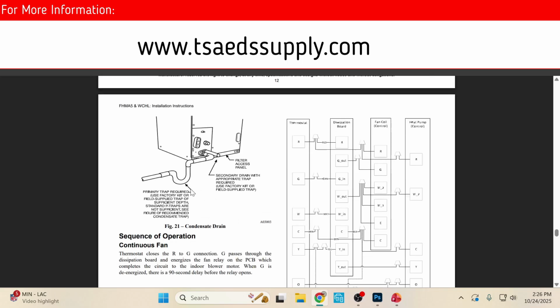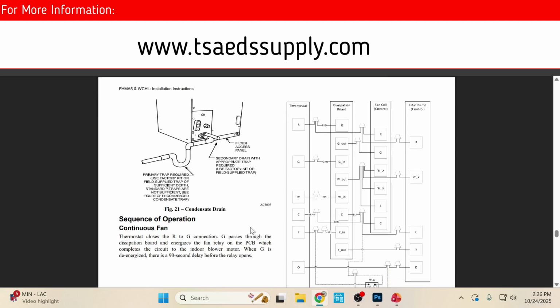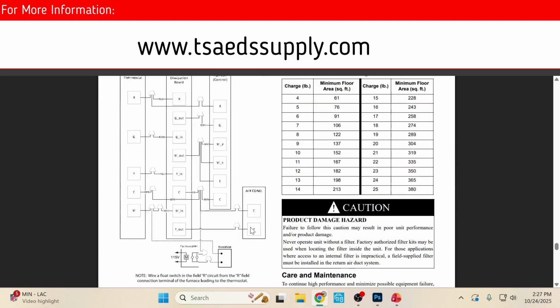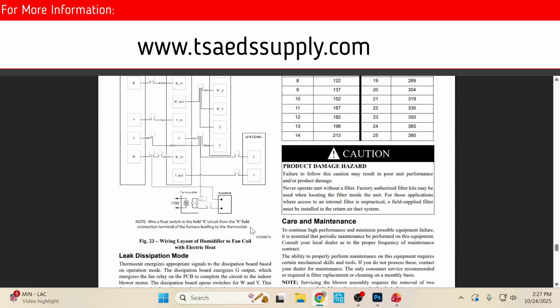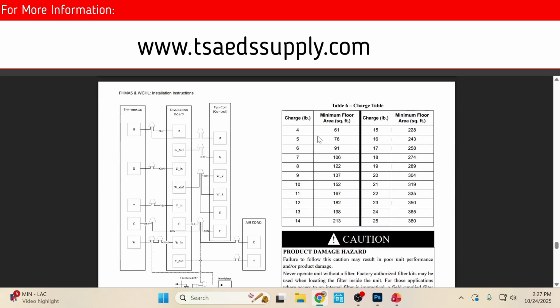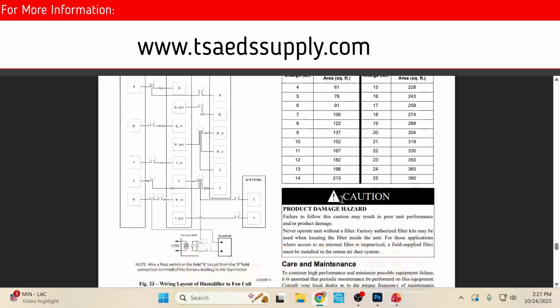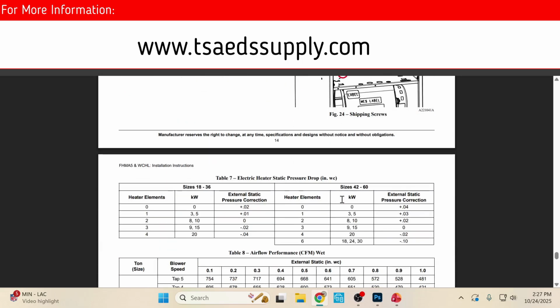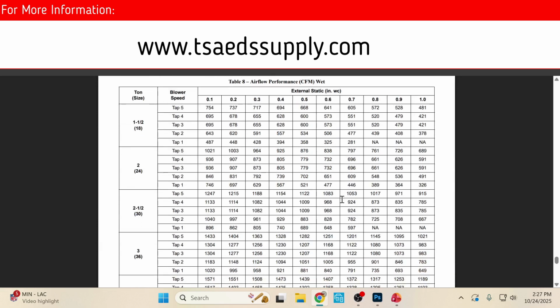Again, here is the big U-trap. Make sure you're looking at this manual when you actually set your traps up. This is something you're going to see in the manual: if I have 8 pounds of charge in my system, I have to make sure I have 122 square feet minimum, so that if there is a dissipation system or there is a leak, I've got enough room that it will not be flammable when it discharges. So here's where I wanted to get to, this chart right here.